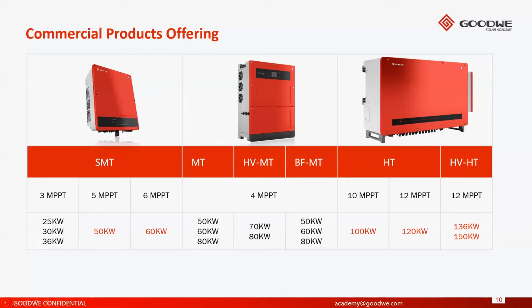Right now, we also have our MT range, which is the current go-to inverter for large commercial PV plants at this very point in time. In this range, we have 50, 60, 80 kilowatts. We do have a high voltage MT inverter. High voltage, I mean by the output being 480 to 580 volts in the 70 and 80 kilowatt range. And this inverter needs a step-up transformer to connect to the high voltage or the distribution network.